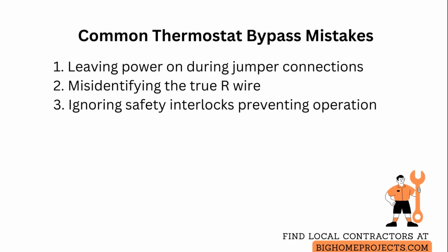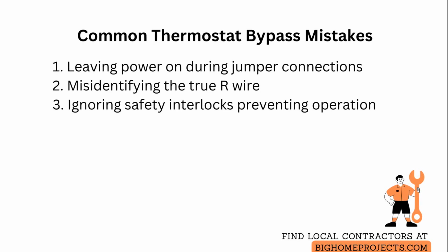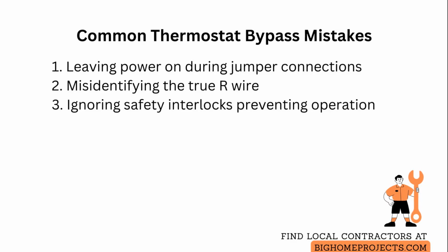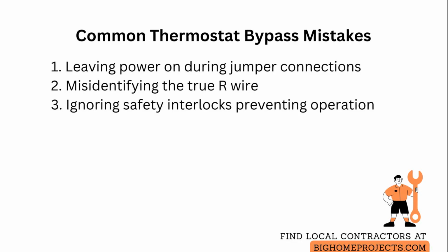Another issue is misidentifying the R wire when there are multiple red wires or a red common loop. Trace the red lead back to the transformer or use a voltage tester after power off and on to confirm which conductor is the true R.